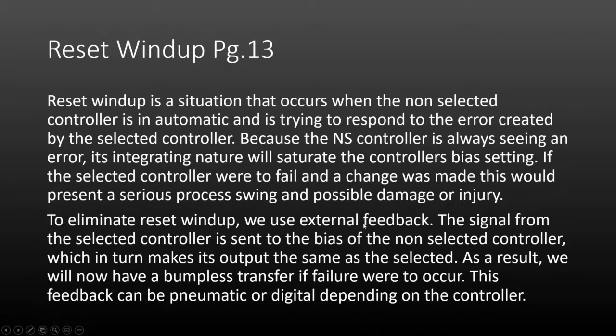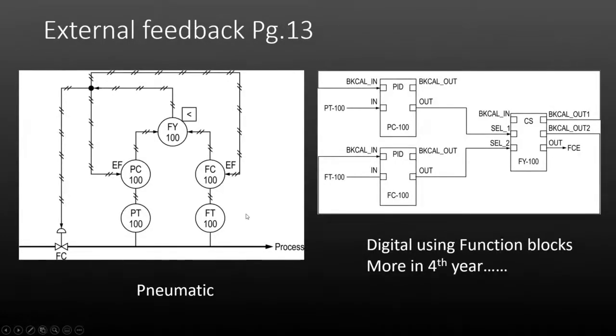The external feedback can be either pneumatic or digital depending on the controller. Here's what it looks like pneumatically — it is very simple. I have this controller, another controller, and a low selector taking a process measurement. The pressure controller is the low one right now — it sends its signal to the selector, the selector selects that signal and sends it out to the valve.